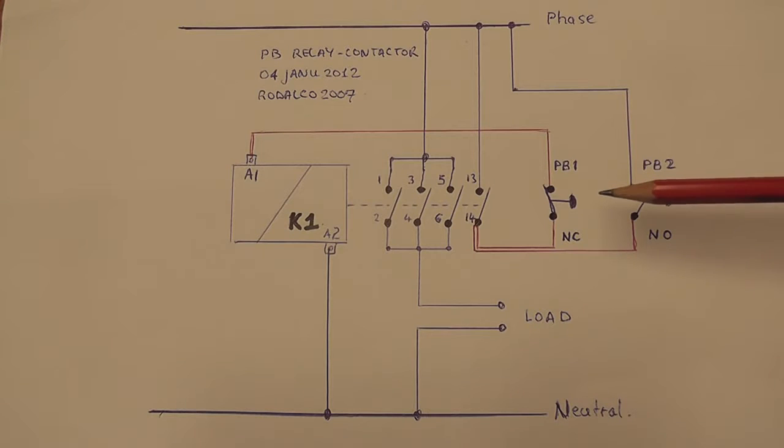Push button one. That's normally closed. That's for the off position and push button two is normally open. And that's for closing the relay into the supply. And then the load is connected onto these two terminals, to the orange connector with a lamp or the heater connected to.